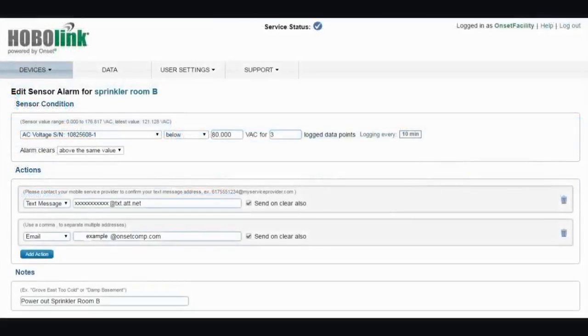Here's an image from that alarm page. I didn't want to include the actual telephone number or email address of the person being notified. But basically what we're saying is that if our AC voltage goes below 80 volts AC for 3 logged data points, we want to be notified. So that equates to 30 minutes on a 10-minute logging interval. And this person is going to get a text message and also an email. And we did the same thing with temperature, except we used 35 degrees Fahrenheit.